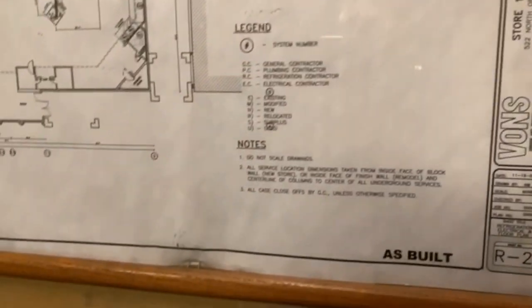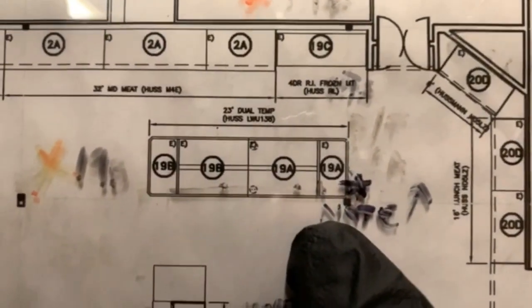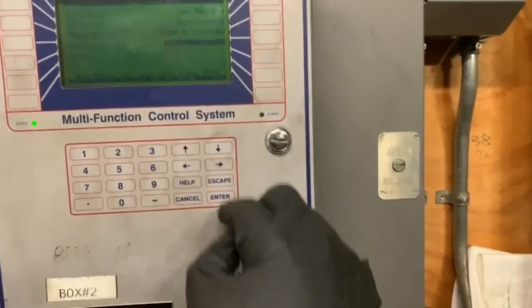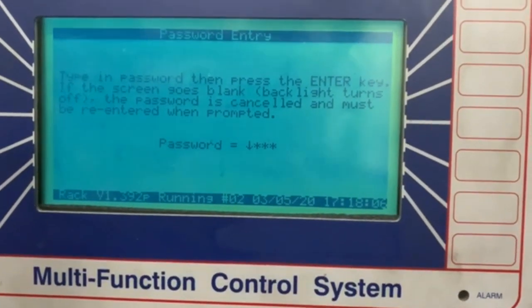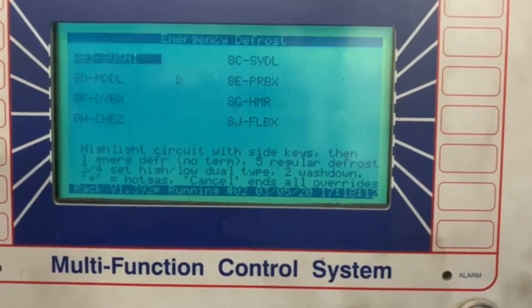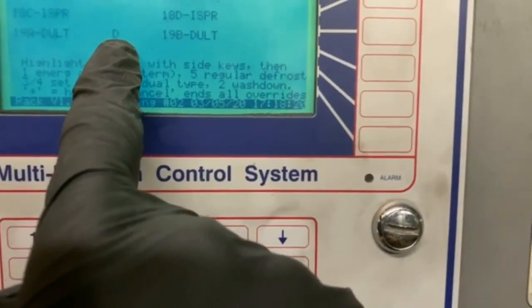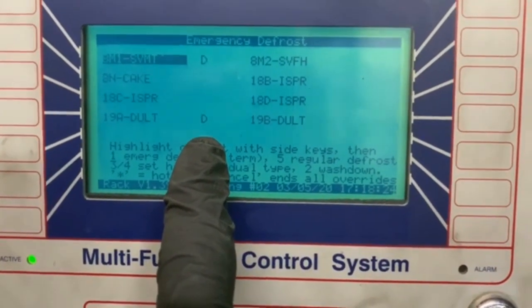I'm over here in the motor room. Here's the map, here's the front of the store, here is my case I was working on — 19B. I'm gonna go ahead and put that in defrost. This is the main menu — put in the code, enter, scroll down, find my case. And what do you know — it's already in defrost by the time I get out here. Perfect timing. I'm gonna go downstairs now, check defrost, make sure all my heaters are working.